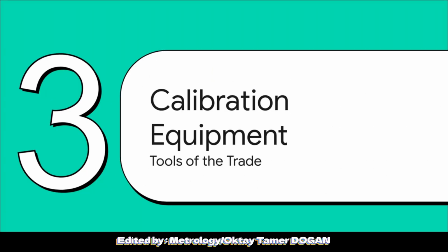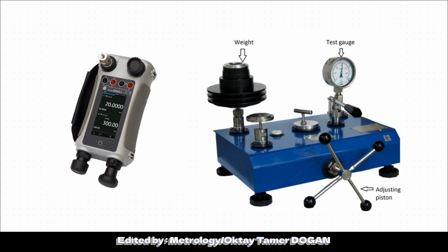Okay, Section 3. Calibration equipment, the tools of the trade. Let's move from those abstract definitions and look at the actual physical tools that make precision measurement and, more importantly, precision calibration a reality today. Nowadays, we have these highly advanced digital calibrators. They use complex electronics and super precise internal sensors to generate and measure pressure. But honestly, the pure physics of it really shines in a traditional dead-weight piston manometer. This device is the crucial bridge between theoretical pressure and practical calibration. It literally uses known physical weights, physically pushing down on a piston that has a known surface area, to generate an exact pressure. Again, force divided by area. It's essentially Torricelli and Pascal's discoveries engineered into a perfect physical reference standard.